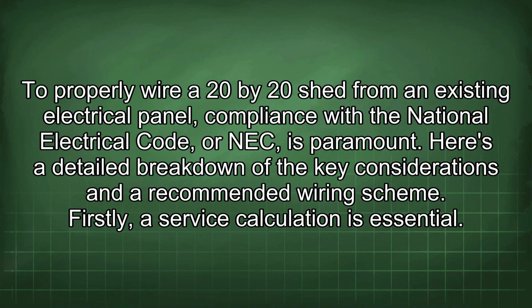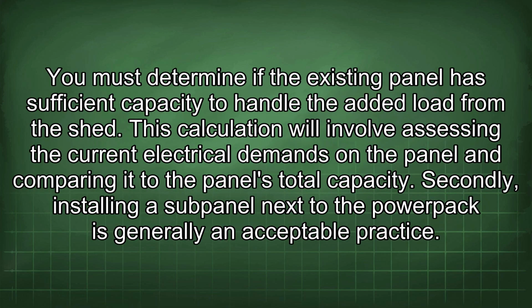To properly wire a 20 by 20 shed from an existing electrical panel, compliance with the National Electrical Code, or NEC, is paramount. Here's a detailed breakdown of the key considerations and a recommended wiring scheme. Firstly, a service calculation is essential. You must determine if the existing panel has sufficient capacity to handle the added load from the shed. This calculation will involve assessing the current electrical demands on the panel and comparing it to the panel's total capacity.